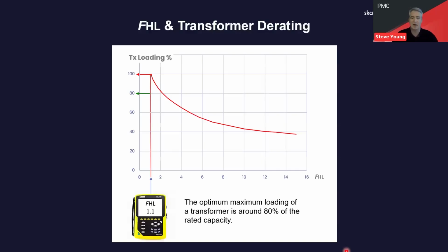In order to understand that a little bit better, we can populate an FHL curve, a harmonic loss factor curve. This is a typical harmonic loss factor curve, and let's consider it as the one for a distribution transformer. Along the horizontal axis, we have a harmonic loss factor value, which is measured during typical peak demand by the instrument. Up on the left-hand side, we see the transformer capacity. Let's use an example of 1000 kVA, from 0% loading up to 100%. If we have very little, an insignificant amount of harmonics, and so little heat and vibration, then there's no need to derate significantly. So we might consider that this 1000 kVA transformer has an optimum limit of 80% without any harmonics.